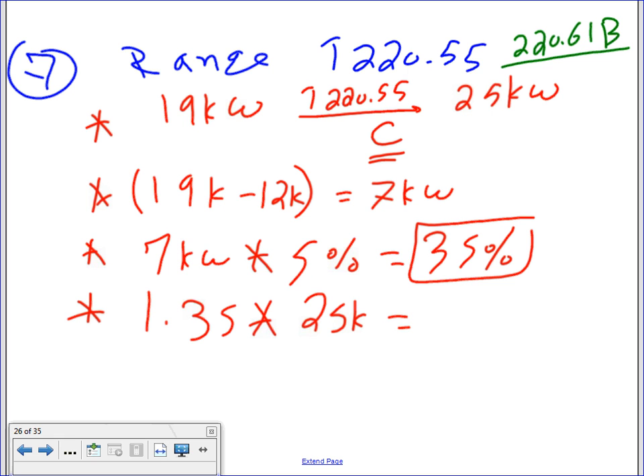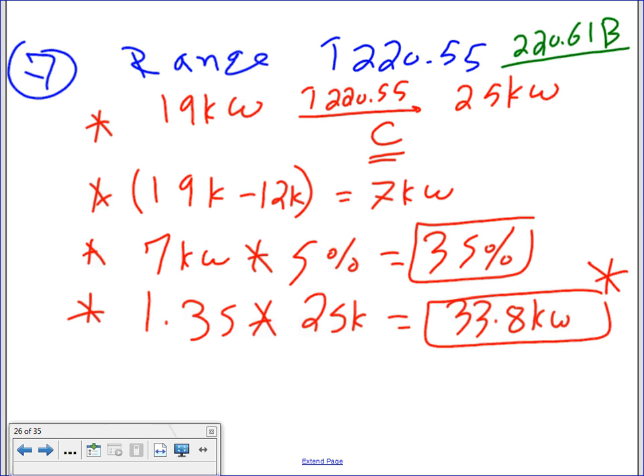And your total demand for this step is 33.8 kW for all 10 of them. Can you guys appreciate that? If you want to, take Adam, multiply the 19 by 10. That'll get you 190 kW, down to 33.8 kW. Major difference for ranges. From 190, because there's 10 of them, down to 33.8. So that's the number that you're going to use for sizing your service.